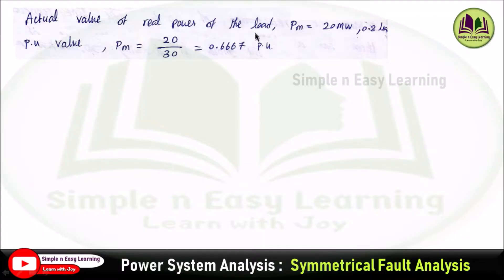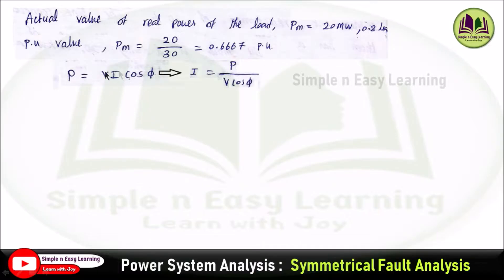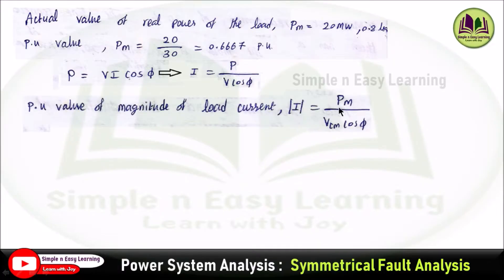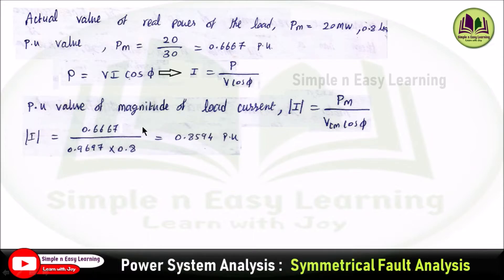The actual real power of the load P_M equals 20 MW (20,000 kW) at 0.8 leading power factor. Per-unit value equals actual value divided by base value: 20 divided by 30 equals 0.6667 per unit. Since P = VI cos φ, the load current magnitude I equals P divided by (V_TM × cos φ). Substituting per-unit values: P_M = 0.6667 divided by (V_TM = 0.9697 × cos φ = 0.8), giving a load current magnitude of 0.8594 per unit.